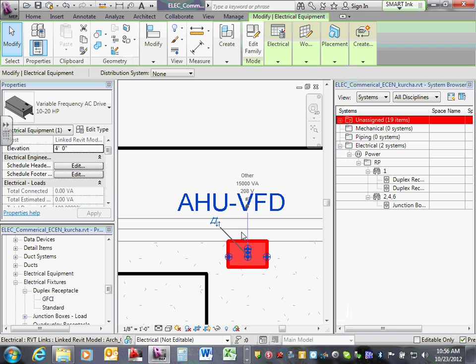There are two ways. There's the Chad Curtis way for you guys to do it here, which is you take the full load amp from the motor, multiply by 480, multiply by 1.73, and do all the math. And there's the rule of thumb engineering way - a horsepower is equivalent to what? A kVA. That's a good approximation for this, for Revit.